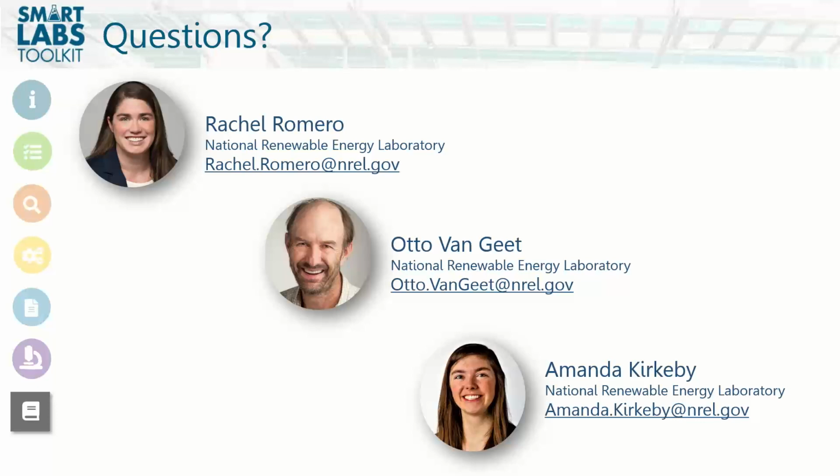Great. Thank you, Otto. So the next question is, how does a system like Aircuity play into this? Yeah, excellent. I'll take that one too. On my slides, I talked about demand-based ventilation. The first and easiest of those is occupancy sensors, and then setting the ventilation to an unoccupied mode based on the ventilation risk assessment that Amanda described. If you want to take that a step further, you can actually do a chemical sensing system. That's what this Aircuity is. It draws air from the lab space, analyzes it, and looks at things like total VOCs, volatile organic compounds, and can reset the ventilation rate up if some of those are detected beyond a certain limit.